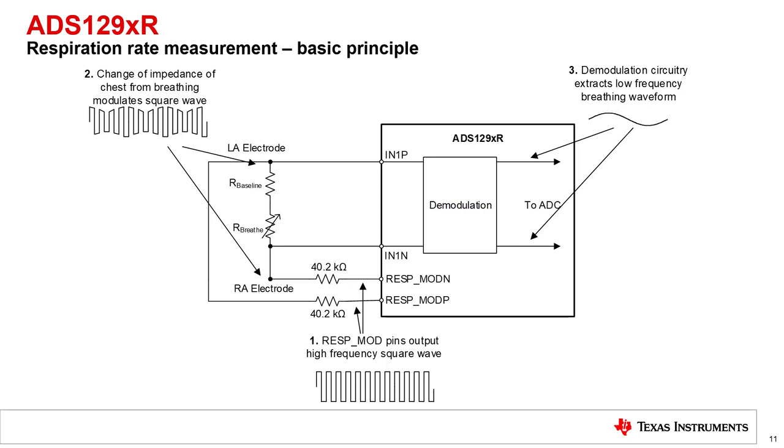The DC common mode voltage in the demodulated waveform results from the total constant impedance in the respiration signal path. The amplitude of the demodulated waveform is the result of the changing impedance, R breathe. This waveform is then output from the ADC for analysis by the customer.